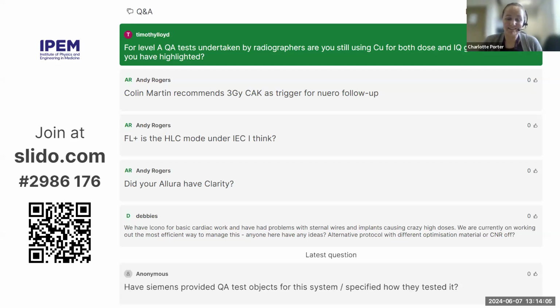The problem is, of course... Oh, sorry, I was just going to say, in Leeds, we're unable to source some additional perspex at the moment. So what we've done with the existing equipment that they've got is to tell them to use that service and regulation program that doesn't use contrast noise ratio regulation. Now, obviously, that's not necessarily representative of what the system's doing clinically, but it at least gives us an idea of whether there have been any large scale changes in the performance of the detector and the system. So that's what we've been doing for the time being, but we would like to work towards being able to test the actual clinical programs, obviously.